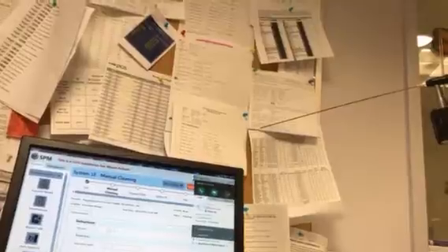Then it goes to the manual cleaning, where you can have different types of things in the document. And the star means it's required. So if I advance past it, it's not going to check it off yet until you check it. Here's my channel check, with instructions to do that, and whether you pass or fail. Here's the disinfection.